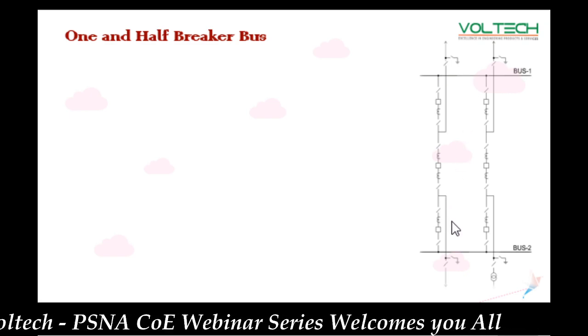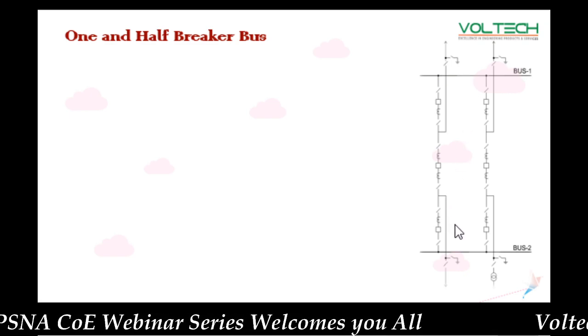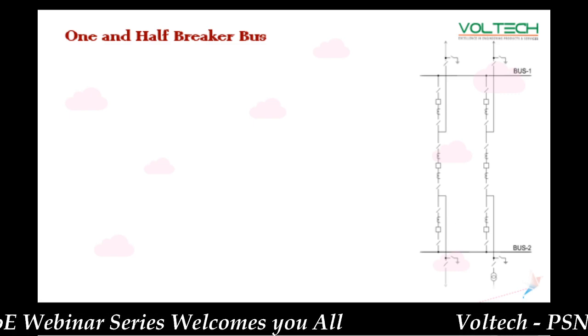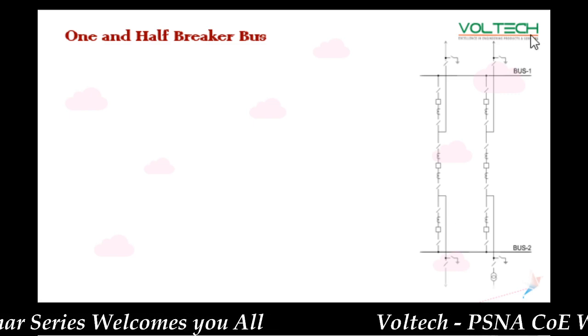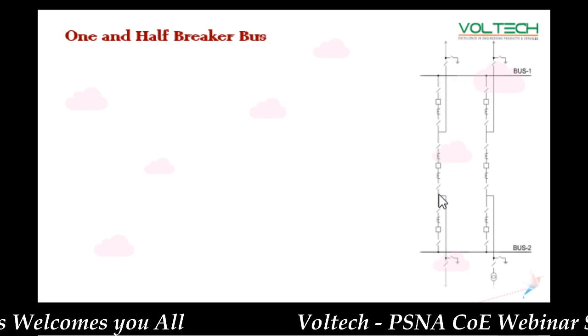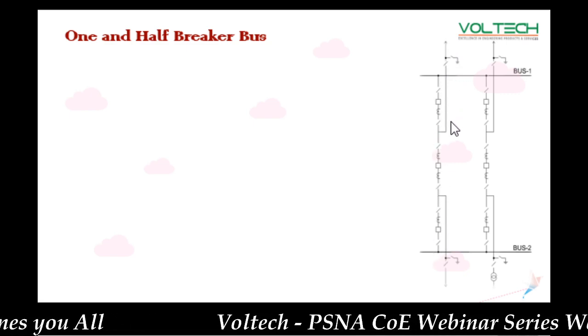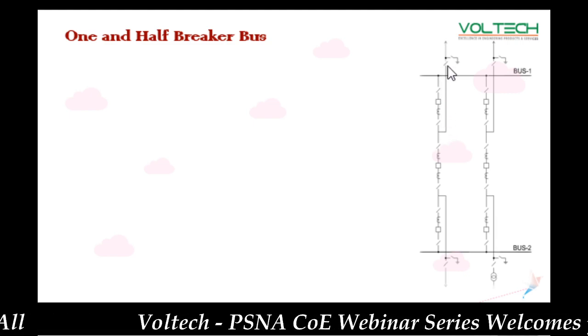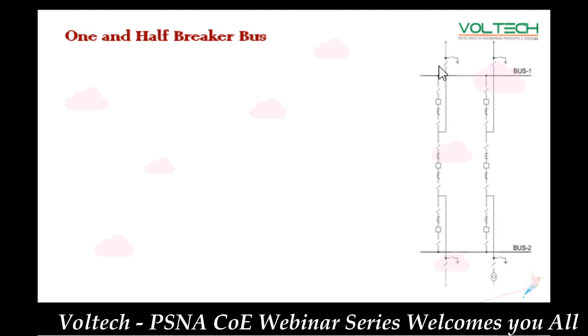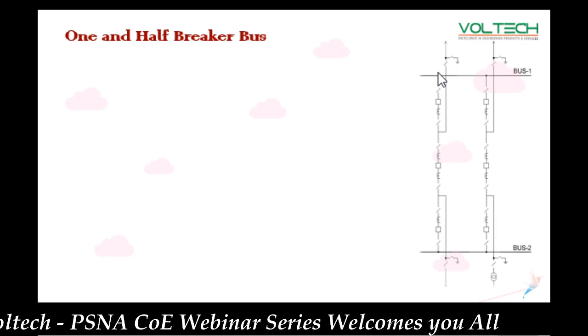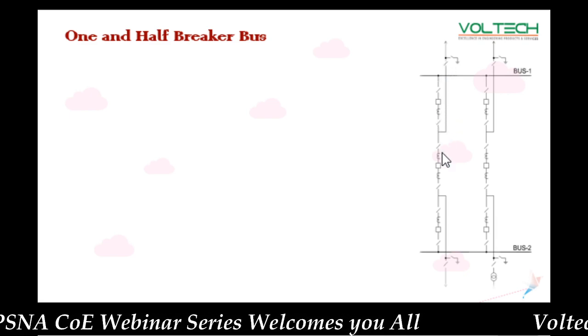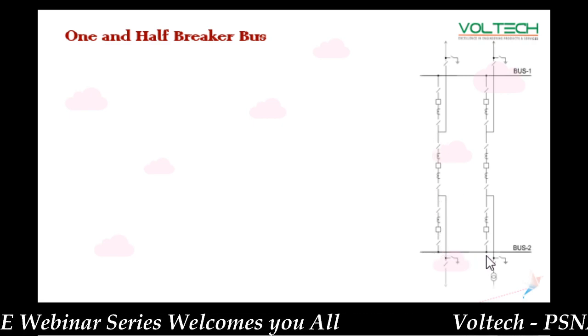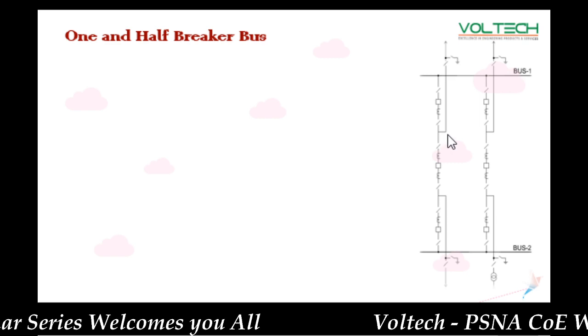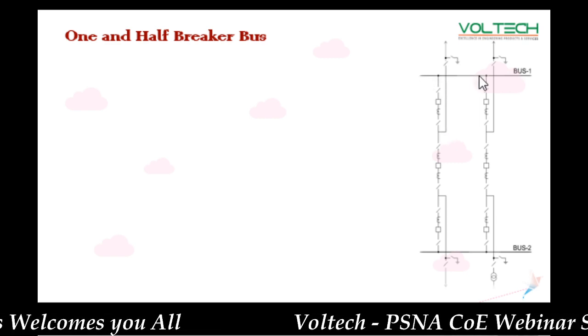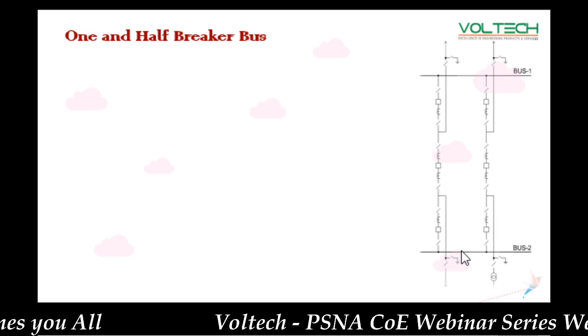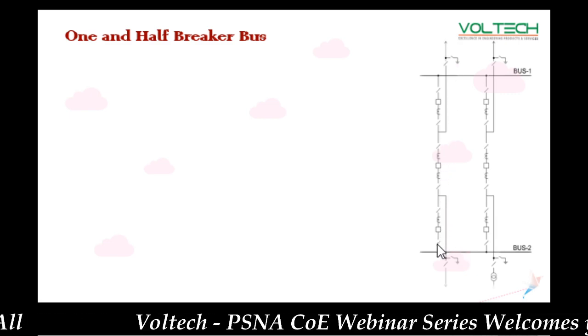Here also we can use maintenance and also, without any interruption, we can evacuate the power. So here it's showing the three breakers. Whenever there's a fault on a line or load, this is connected to the bus through breakers like this, and also we can connect to the second bus. One line or source is connected to bus 1 and also bus 2. So this is the type of arrangement we are using.